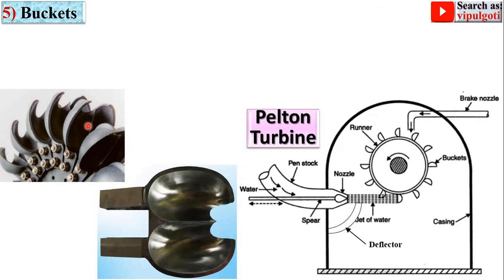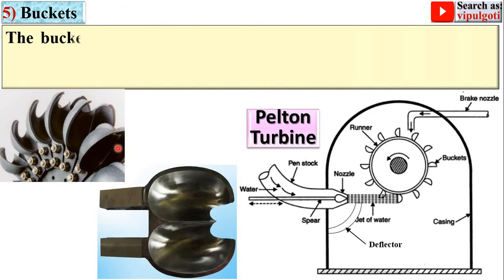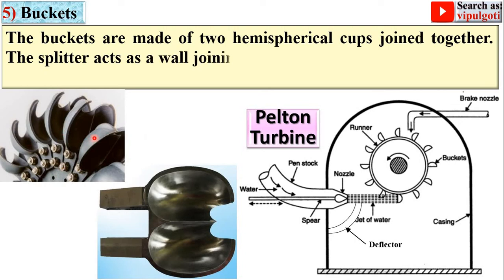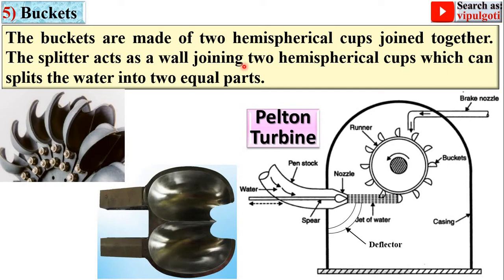Next part: the buckets. The buckets have a double hemispherical shape, made of two hemispherical curves joined together. The splitter acts as a wall joining the two hemispherical curves, which splits the water into two equal parts.